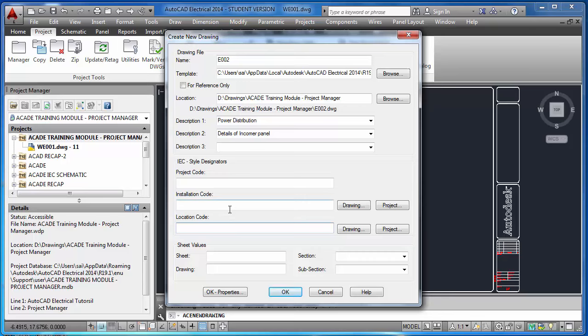Okay, the plane is the installation and the location is its cockpit. Let us assume that the cockpit is my panel number 1, P1. I am putting P1 or 01 TT, whatever you can put. P1 is my location and this is my lineup 1. A huge number of panels, many panels, are clubbed together. That is called a lineup. That is my installation, and this location is a single panel among those. That's all. And section, subsection, again you can put those here, but forget about those, at least for now.